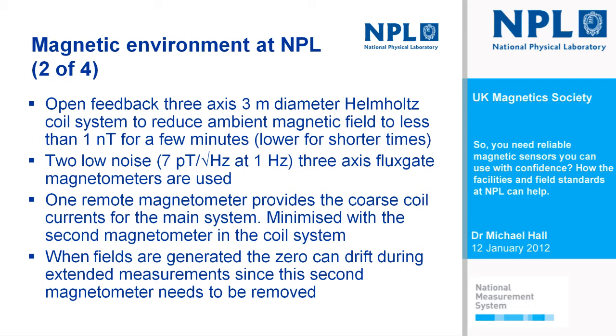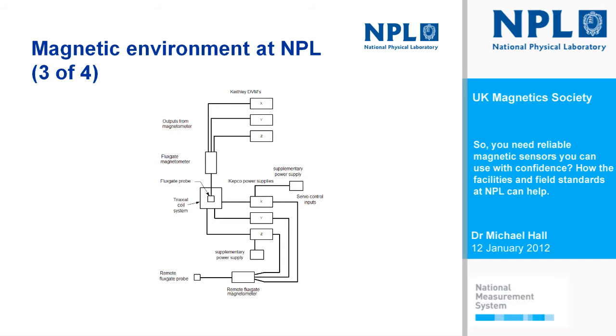Here's a little schematic that shows what I've just described. We have the remote flux gate magnetometer, which is 70 meters away in the garden, and we have the 3-axis flux gate we saw in the picture positioned at the center of the 3-axis Helmholtz coil system. The outputs from each of the axes of the remote flux gate then feed into 3 separate power supplies, servo controlled inputs, which then generate the currents that go into each of the coils of the 3-axis Helmholtz coil system.